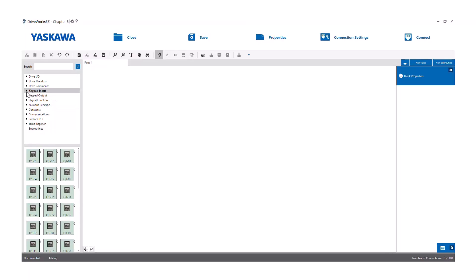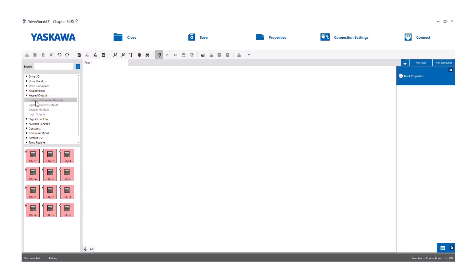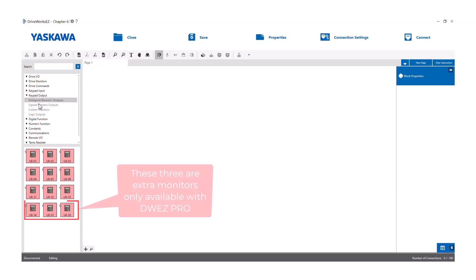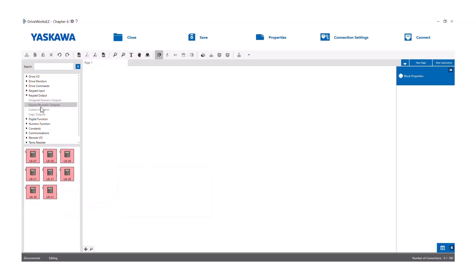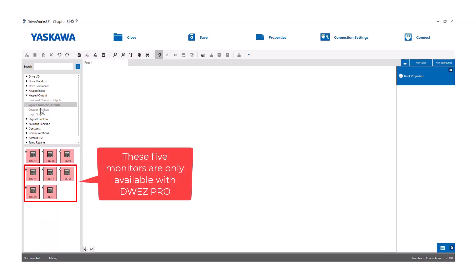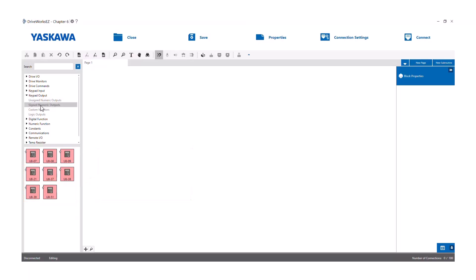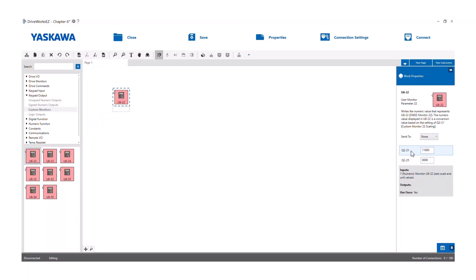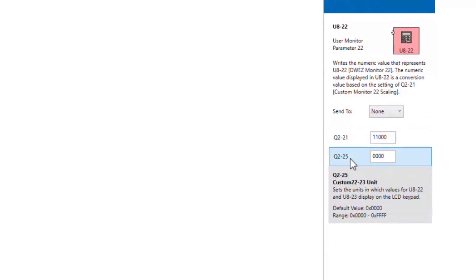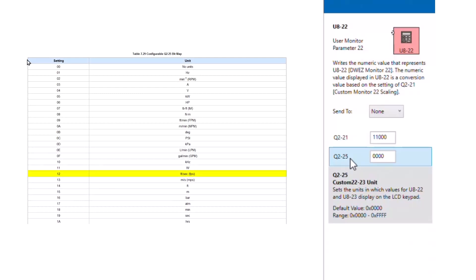We also have keypad output blocks. With these, a numerical value input coming from somewhere else in the program will be displayed on the drive's keypad under different monitors. DriveWorks Easy monitors are all U8 monitors. U801 through U806 and U831 through U833 have unipolar ranges of 0 to 999.99%, while monitors U807 through U809 are bipolar and go into the negative 999.99% range. Keypad outputs U822 and U823 are special bipolar displays — special scaling and special units can be added to the keypad display for both of them. For instance, you could set it up so that a 100% input into the block would cause keypad output U822 to display 150.0 feet per second, or FPS.